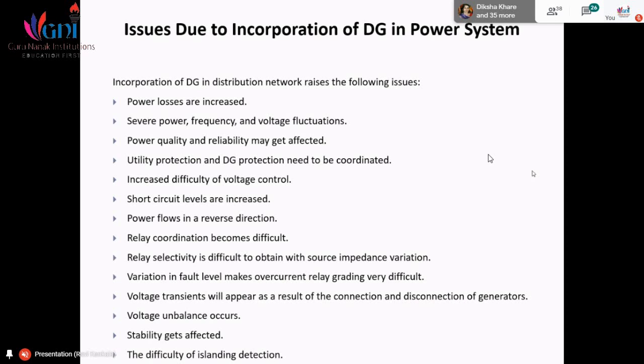So in that case, what is happening? If the utility is disconnected and your DG is not disconnected, then the power is still available. So what will happen? If a wireman has to carry out some maintenance work on the distribution network, though he has shut down the feeder from the distribution substation, if DG sources are connected to that network from the customer end, they are going to feed power into that network, and because of that most of the accidents take place.